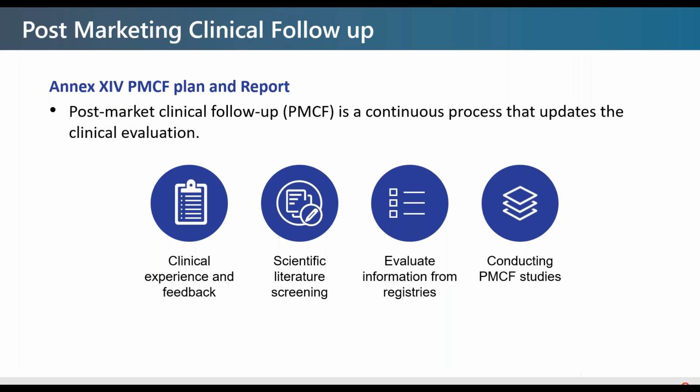So finally, last but definitely not least is post-market clinical follow-up. Post-market clinical follow-up is part of your post-market surveillance. And if you don't do it, you need to justify why you don't need it. And just because you think so isn't justification. But it's a continuous process. It is used to update the clinical evaluation. And the definition is a proactive collection and evaluation of data on clinical performance to confirm its scientific validity and ensure the continued suitability. That's from Annex 14 and Article 61.